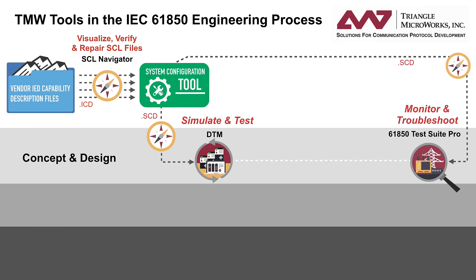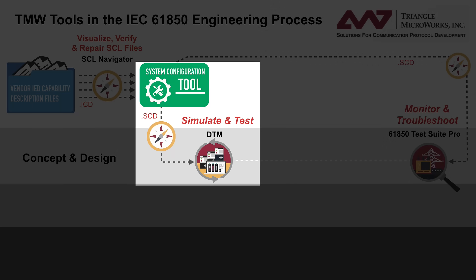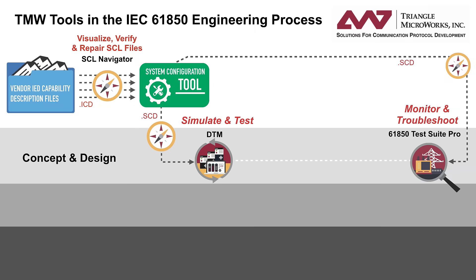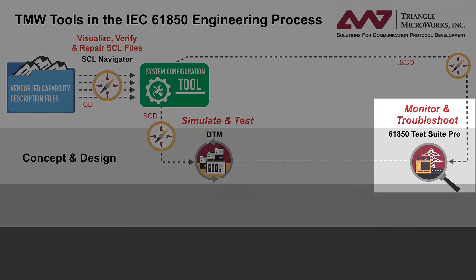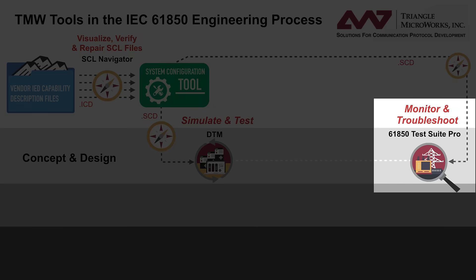The conceptual phase is an iterative process where the system configuration tool creates an SCD file, which DTM uses to simulate all of the IEDs in the substation and create automated tests to confirm individual device behavior. TestSuite Pro is a diagnostic tool that uses this SCD file to monitor, troubleshoot, and confirm the behavior of the new substation design simulated in DTM.